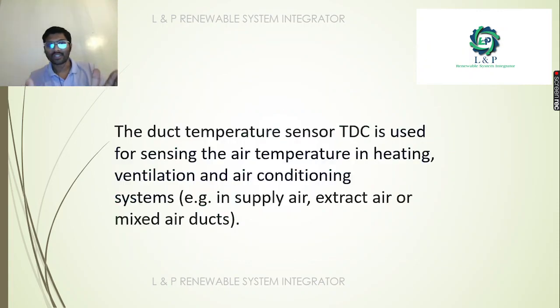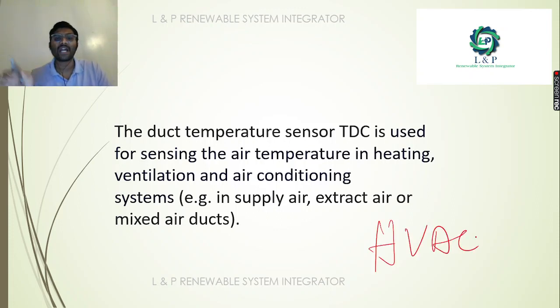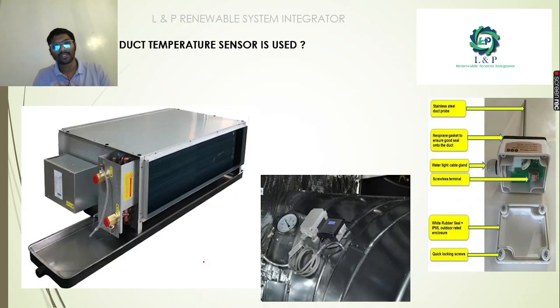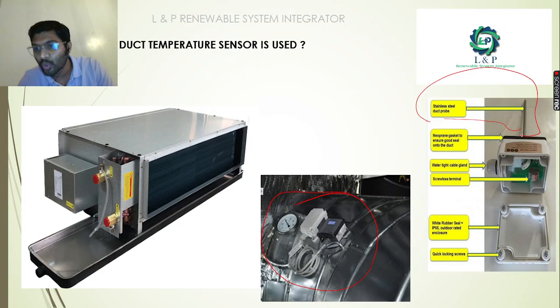So a duct temperature sensor is used for sensing the air temperature, especially in the HVAC system, that is, heating, ventilation, air conditioning systems. We install them in the fresh air ducts, supply duct, return duct, and even in the mixed air ducts. So this is how it gets installed in the ducts. As I told earlier, it will have a stainless steel duct probe, which will be inserted in the duct, and on the outside you can see the external covering.